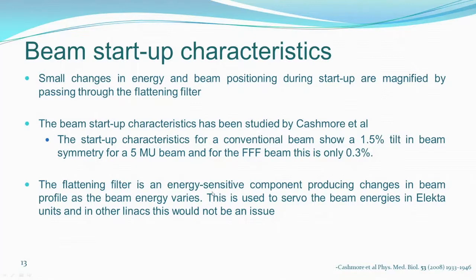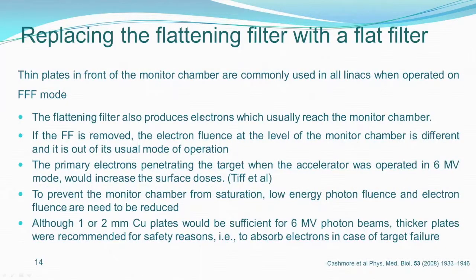The flattening filter is an energy sensitive component producing changes in the beam profile as the beam energy varies. And actually, Elekta uses it for servo of beam energies. So for other Linacs, it's not an issue. For Elekta, this is the servo. So one has to be mindful of that. Now, you don't have a flattening filter, but that doesn't mean that you don't have a filter at all. No, you have now changed the flattening filter with a flat filter, right? So the flattening filter is now replaced by a flat filter.